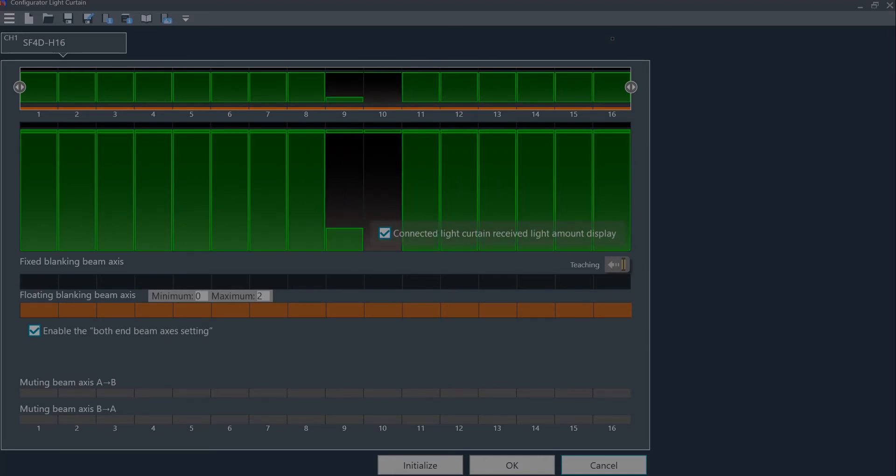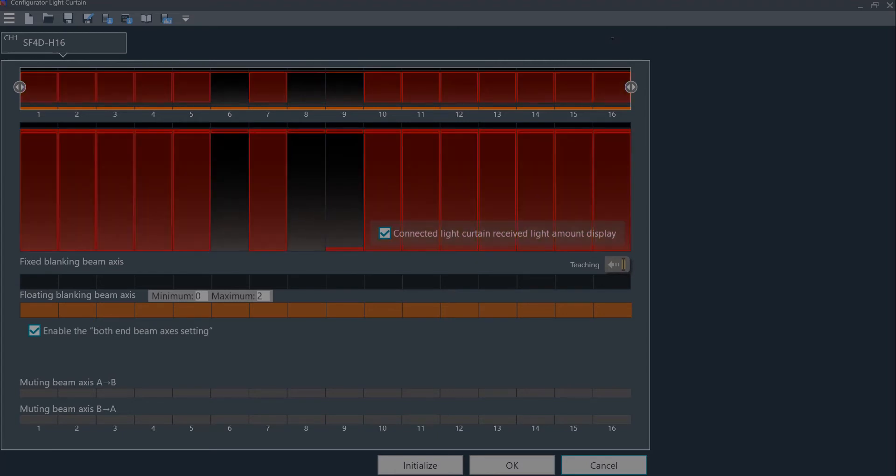As soon as I reach my hand up and block another beam, the light curtain is activated and goes into a safe state. The red bars signify that the OSSD relays are activated.